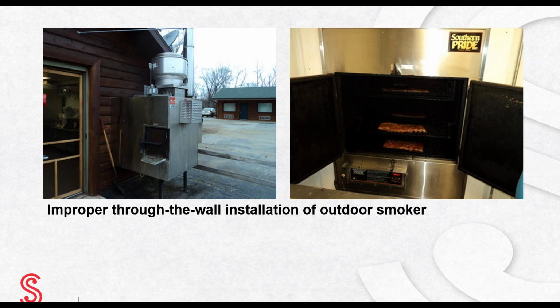The installation kits may consist of 1-inch thick by 8-inch wide insulation board that is installed on the top and each side of the smoker. The manufacturer's installation kit instructions must be followed by the appliance installer. The best practice is to have the oven pass through a non-combustible wall, like a masonry or steel wall, to help prevent the spread of fire if there is an oven fire.